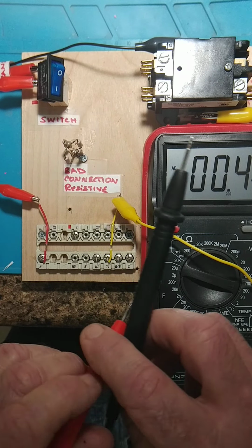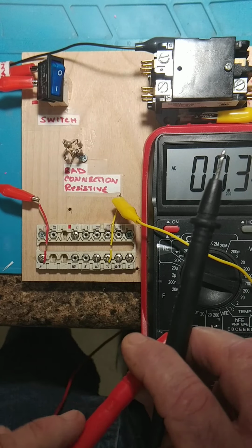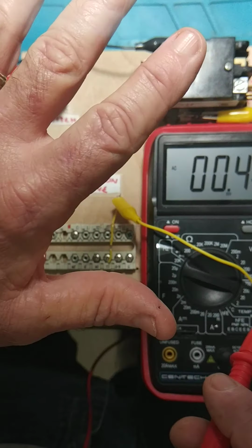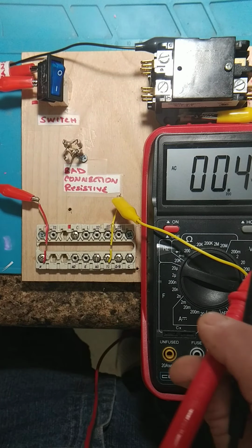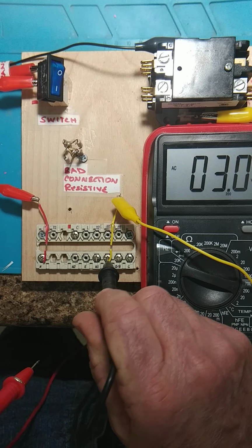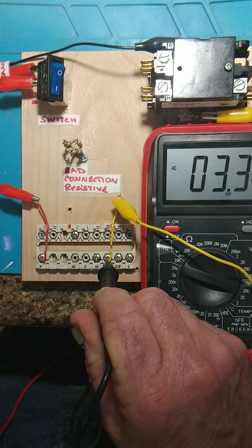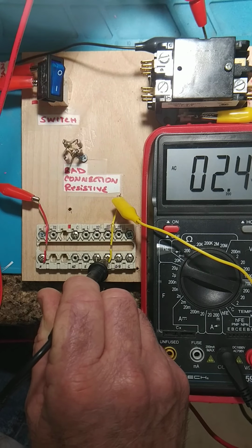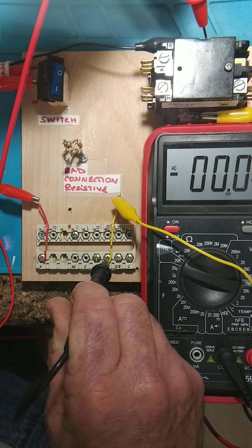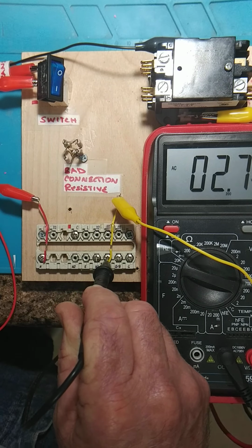So this is where, when you're troubleshooting an HVAC circuit, you can use the existing wiring like a continuity meter. Because I have common here, and I know it's common because when I go from here to my common on my transformer, I have 0 volts. And if I had that common coming over here to my thermostat, it would be the same.